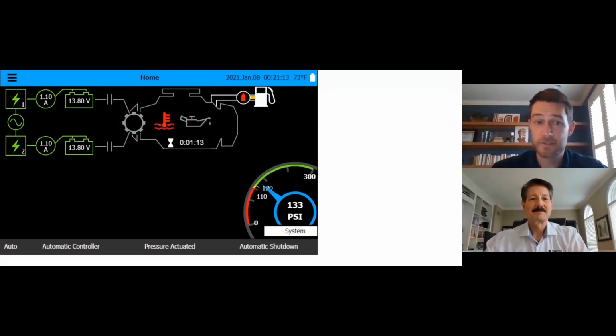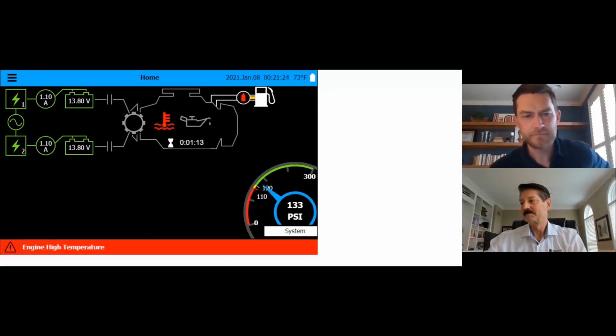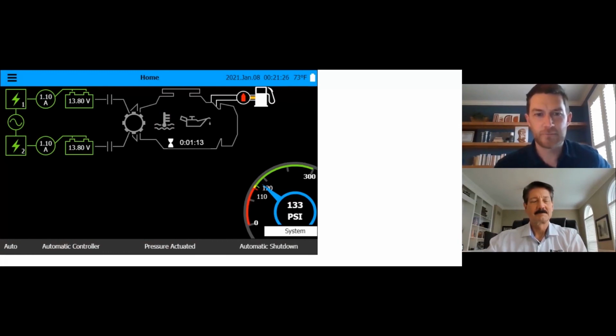So Marty showed the engine alarm, and like you can see now, the engine is gray, so it shut itself off. If it was an automatic start, it wouldn't stop. It would have continued to run even with the high temperature. So the run test gives you a little bit of protection when you're doing a test versus just the auto start.